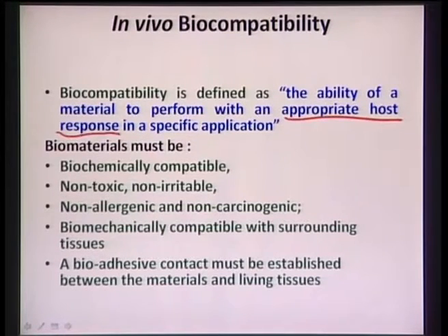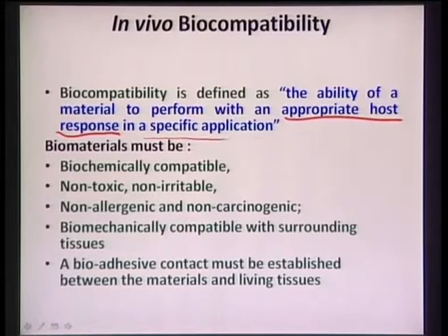Host here means human or animal, so an appropriate host response means that in the area where the material is implanted, there should not be any sort of inflammation or toxicity just because that synthetic material is implanted in that position. And in a specific application means, as I said, biocompatibility is a broad term that has a different meaning for different applications. For blood contacting devices, it is hemocompatibility. For bone forming or bone replacement, cytotoxicity and tissue formation ability are important.